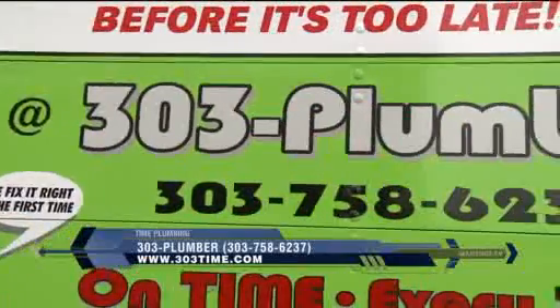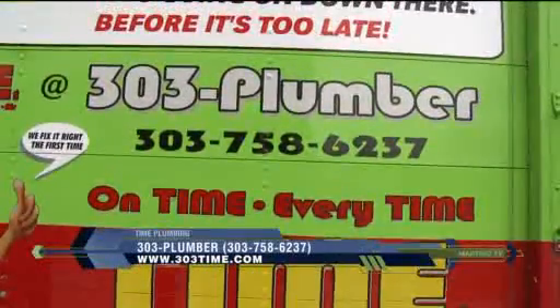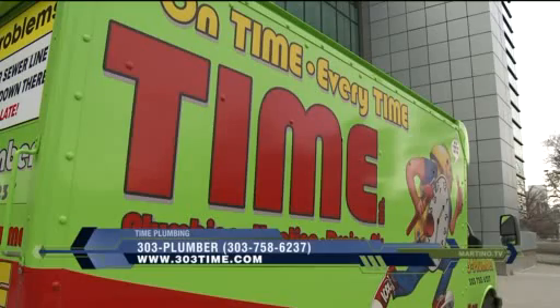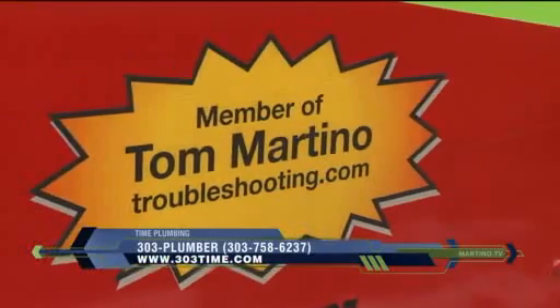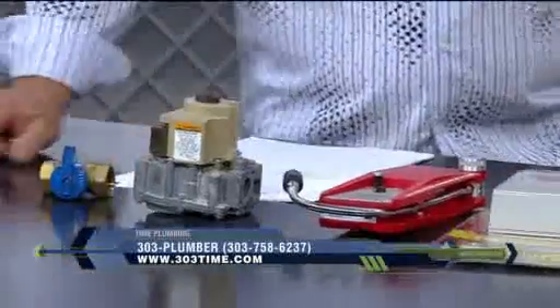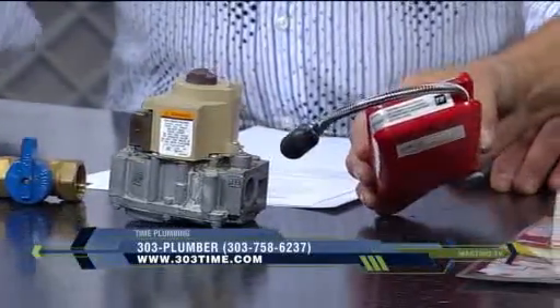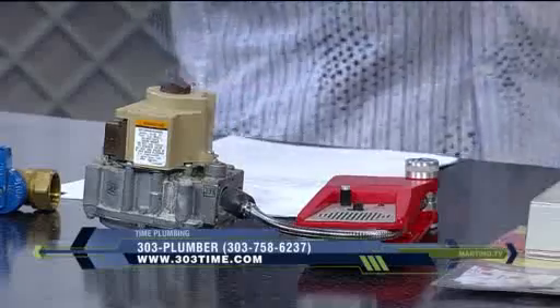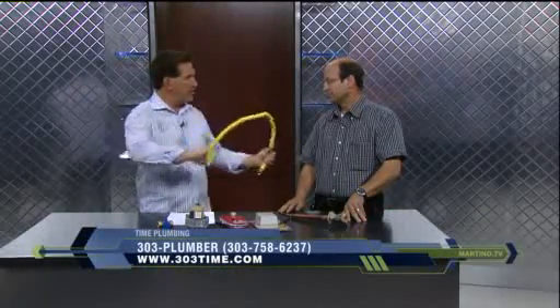Is leaking of refrigerant a common problem? It happens quite often — probably 1% of the systems out there have slow leaks. And of course, we check for gas leaks while we're there. Every house we go into around the furnace or water heater, we run tests to make sure the gas valve's not leaking. This is a gas valve, and this is a checker — you check all of the attachments. Flex hoses, even though they call them flex, they're not necessarily made to be flexed back and forth; they're made to be put in place. You check these for slits — very important.